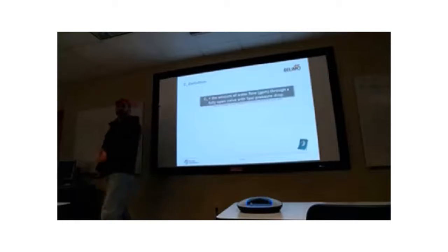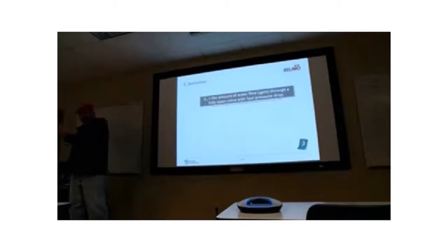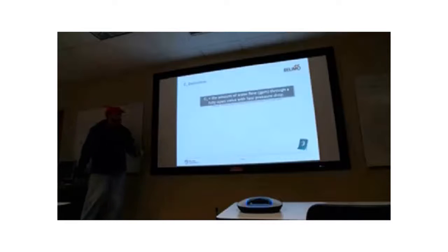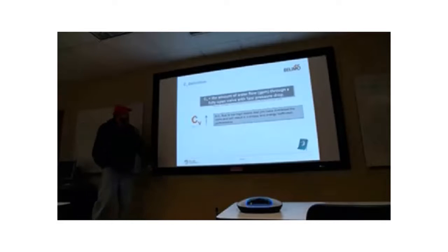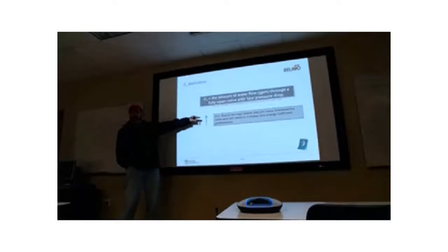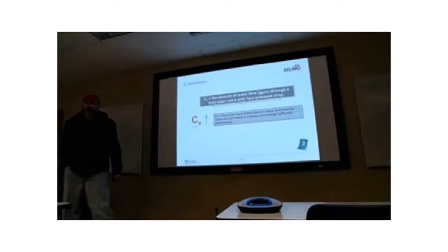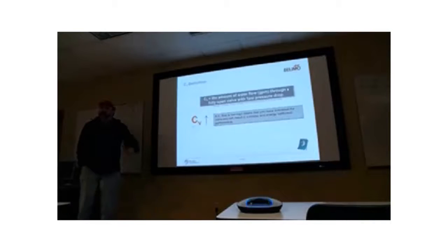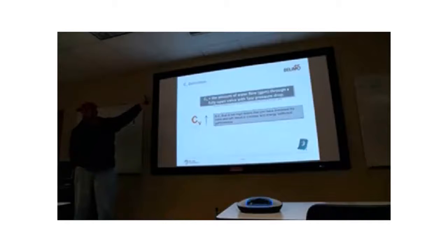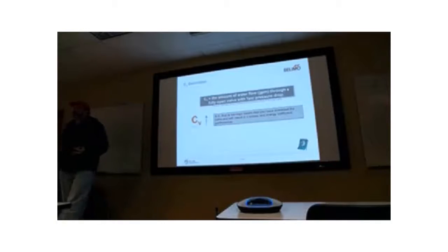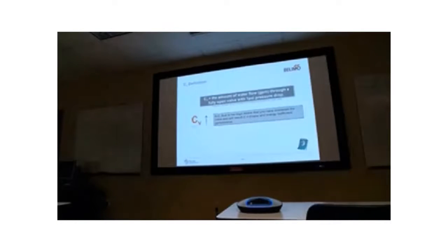That's just the math. But you're going to select that CV based on the target you're trying to reach. You can select that valve based on that CV. So if you select a CV that's too high, meaning you calculate what you think you need but select a valve with a much larger CV, you oversize the valve. Let's think about it. I just want to give you guys, if you oversize a valve, and I know you guys aren't control experts, but you deal with controls in some regard.